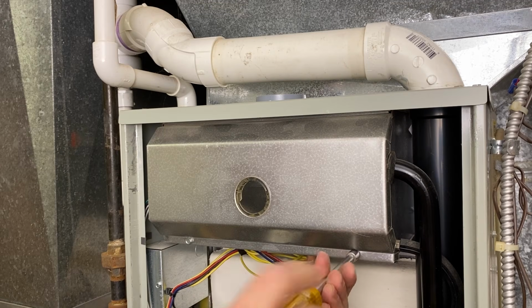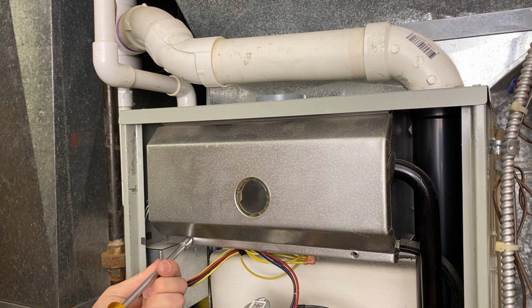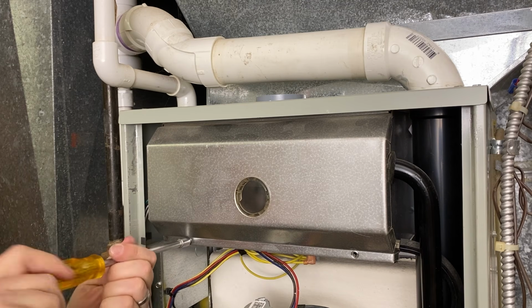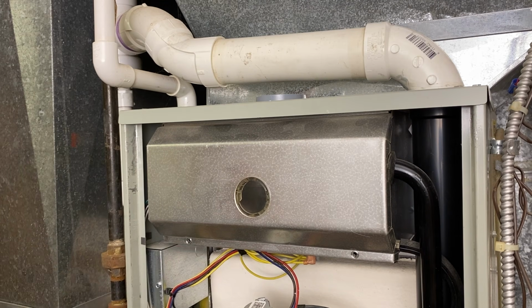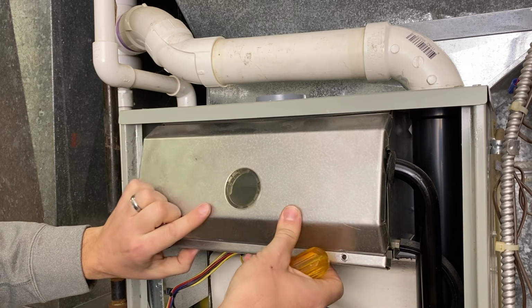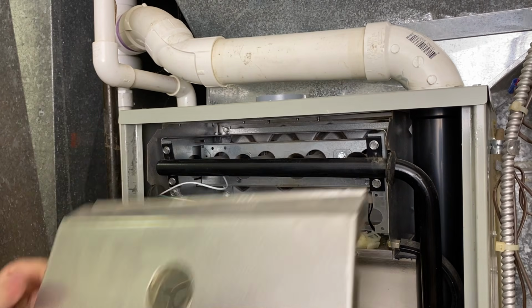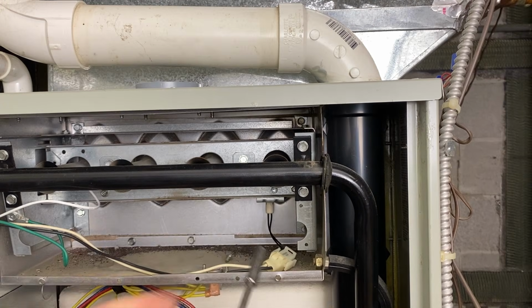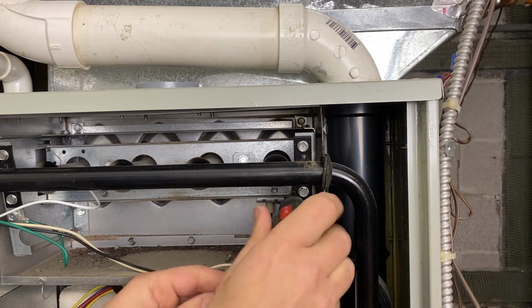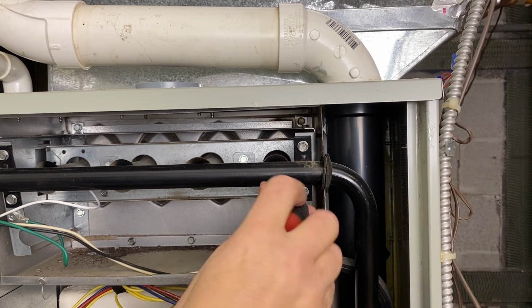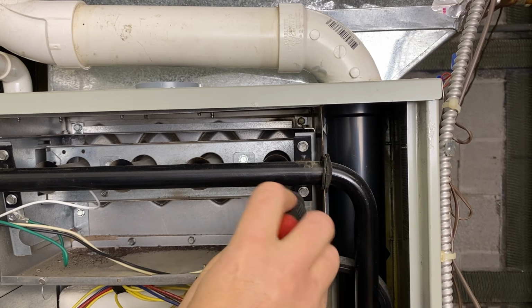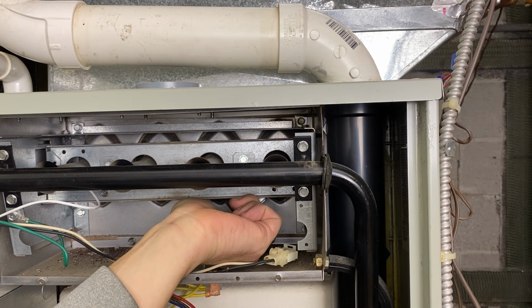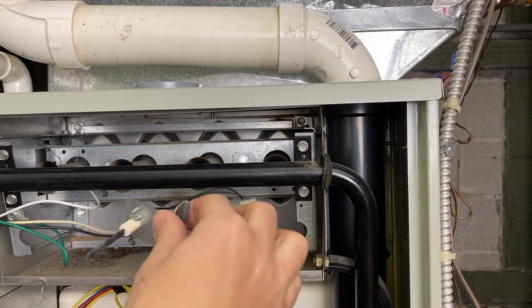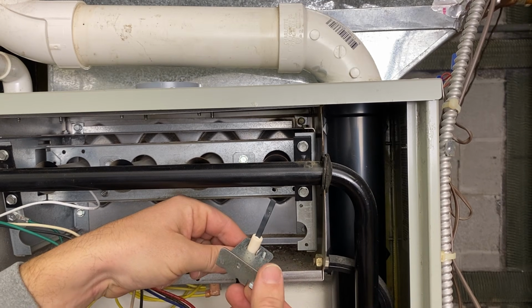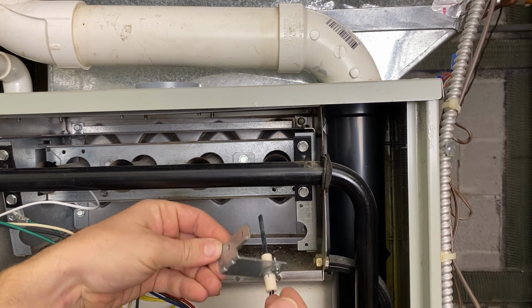All right, so let's get this hot surface igniter replaced. And I'm also going to replace the flame sensor in this video. I bought both parts just because I was also having some previous trouble with the flame sensor. So in this case, it sits on a bracket. There's a couple of 1/4-inch hex screws here we'll take out. So here is our hot surface igniter and the bracket that it fits on.